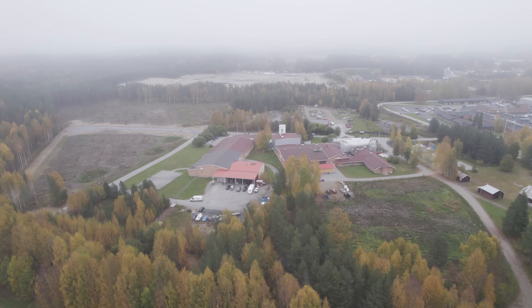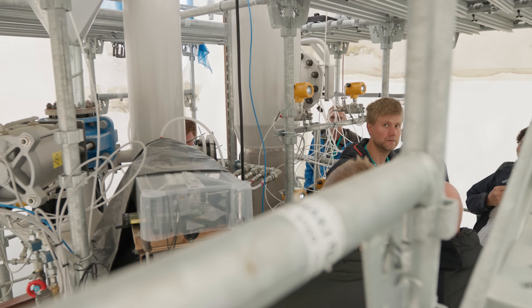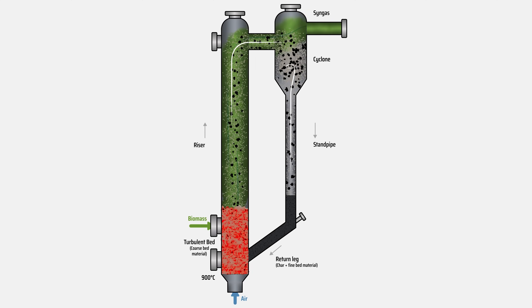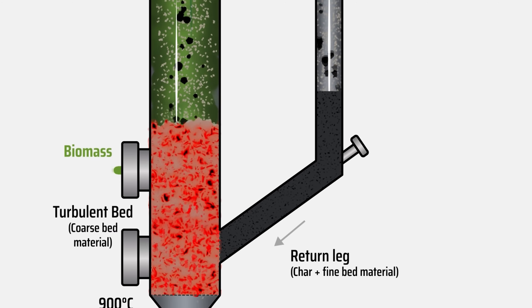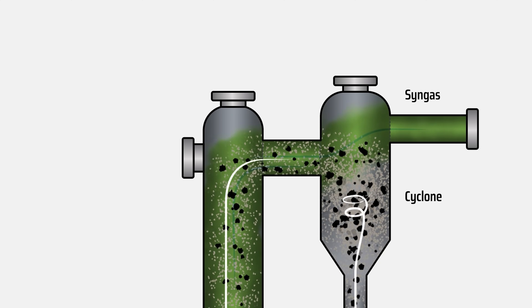At the same time, another core technology was developed in Piteå, in Sweden's far north — the hybrid fluidized bed gasifier. It gasifies the biomass into a syngas, a gaseous mixture of hydrogen and carbon monoxide, which is then used in the combustion chamber to drive the gas turbine. This groundbreaking combination of a hybrid fluidized bubbling bed on the left and the circulating bed on the right represents a world first achievement, as no one has previously implemented such a configuration.